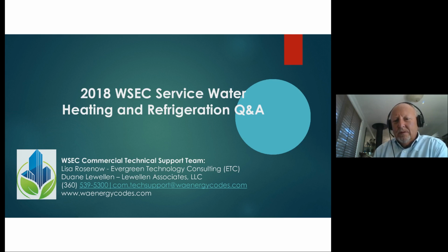So Todd Williams asked, who's verifying refrigeration commissioning? Thank you, Todd. That's a great question. Commercial refrigeration systems have typically been done by a separate kitchen equipment contractor, refrigeration contractor, generally not provided by or designed by the architects or mechanical or electrical. But it is within the scope of work. And so my feeling is that the local jurisdiction should be verifying commissioning of those refrigeration systems. It's included in the scope of the permit.